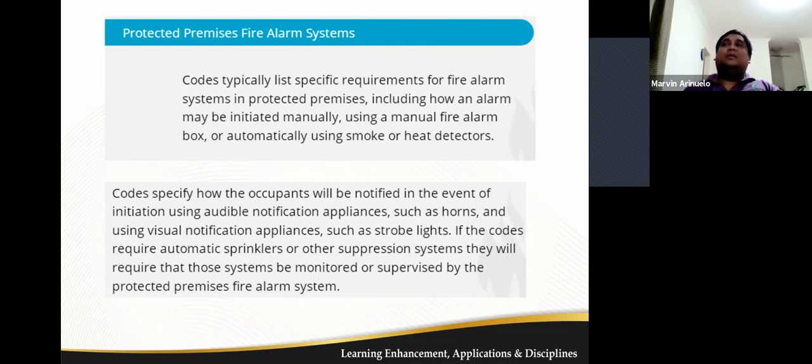So your pre-action valve or deluge valve will not switch on the pump or compressor. It will not relay a signal to your pump to pump water if the smoke detector or heat detector is not triggered or activated. Sometimes at least a second stage alarm, no, because a first stage alarm is normally a false alarm, no.